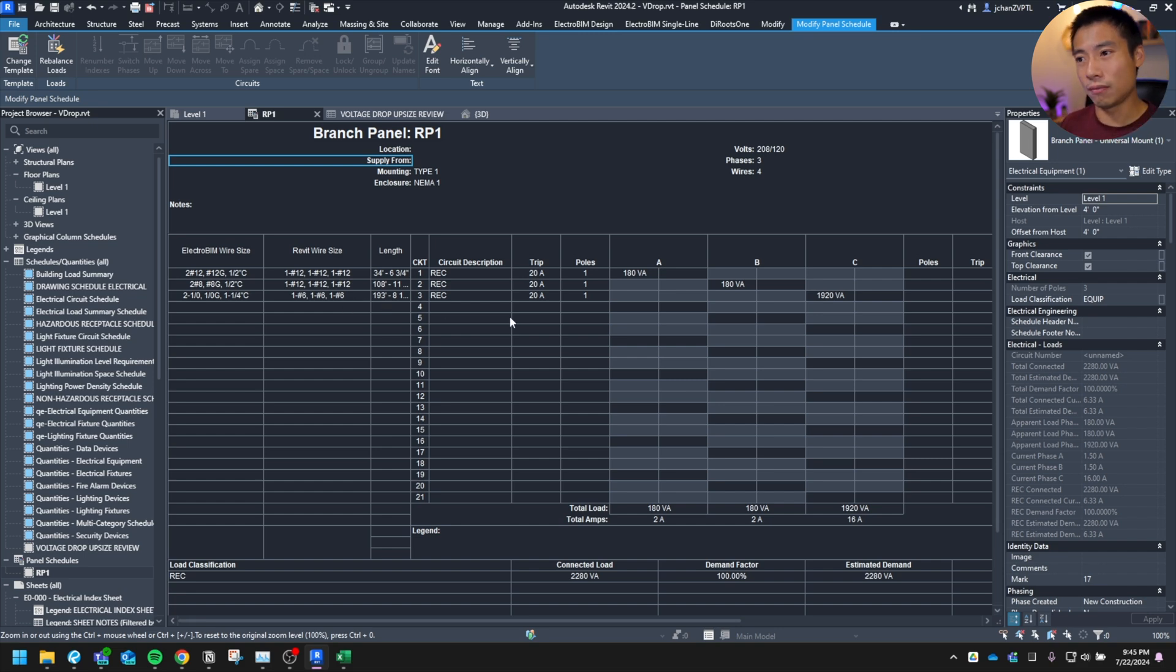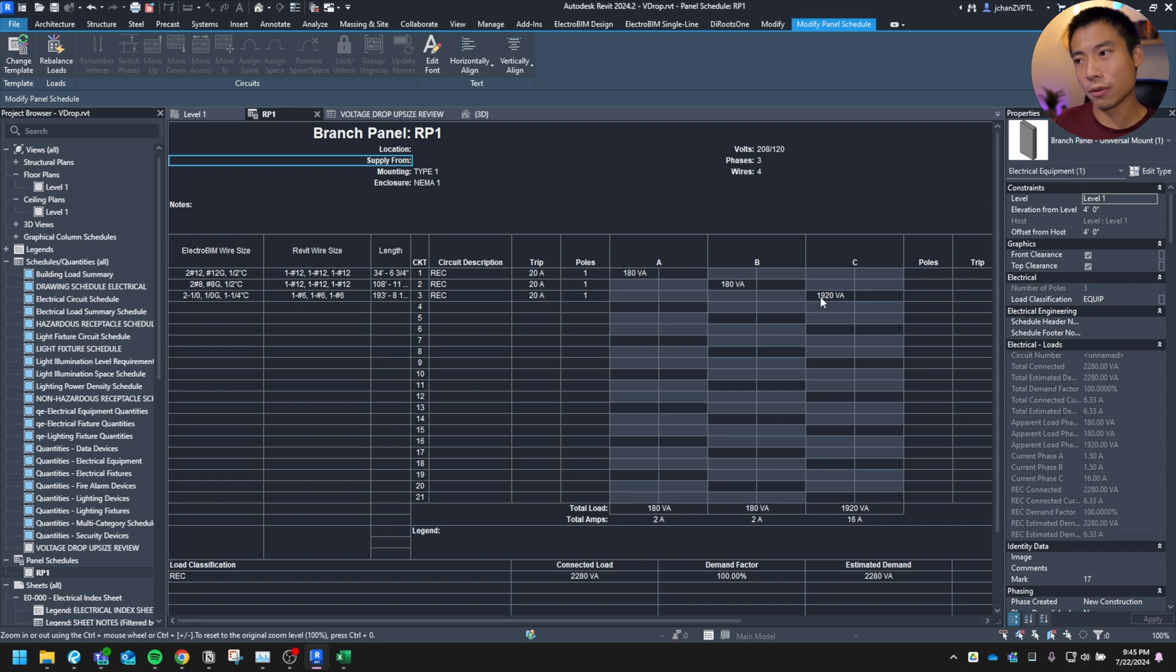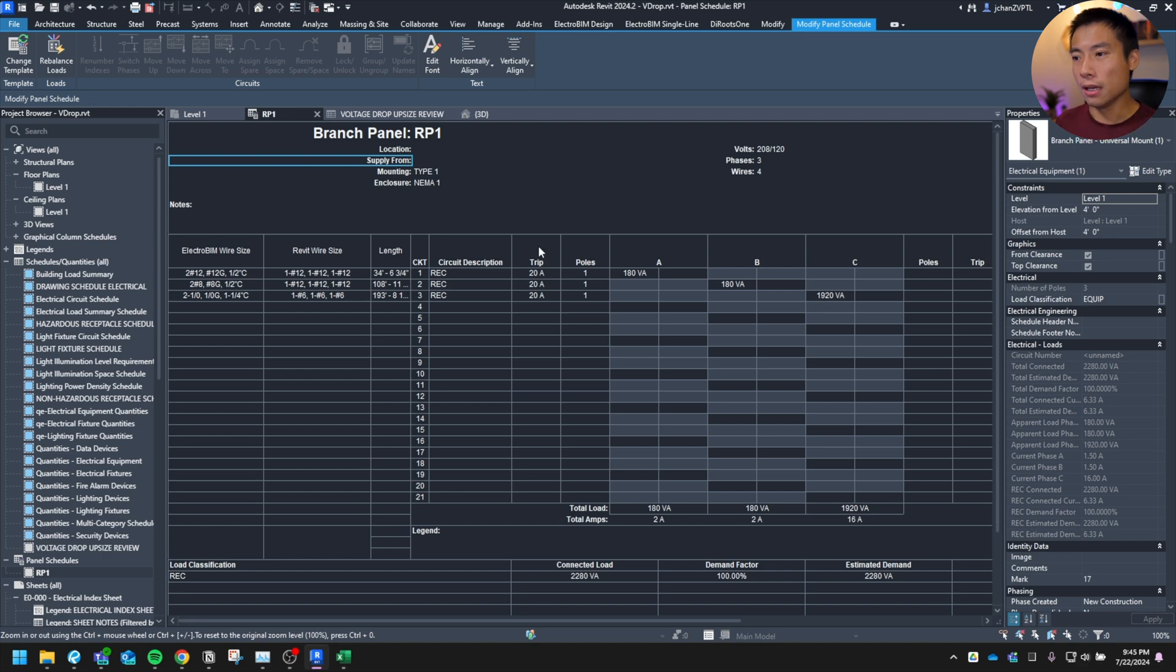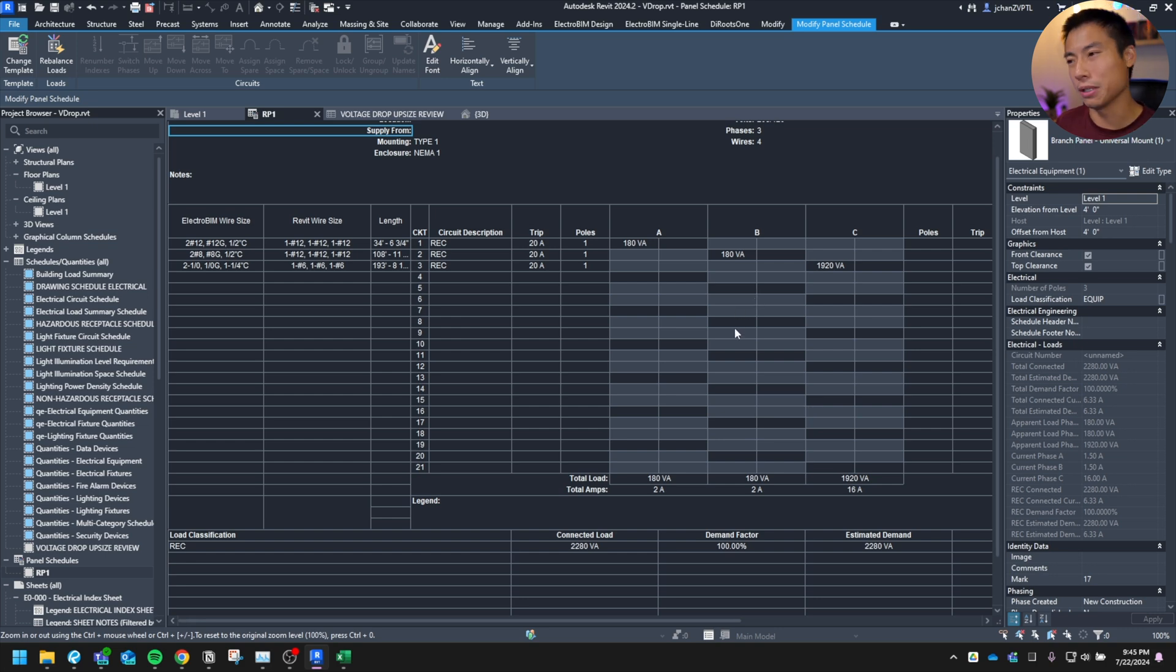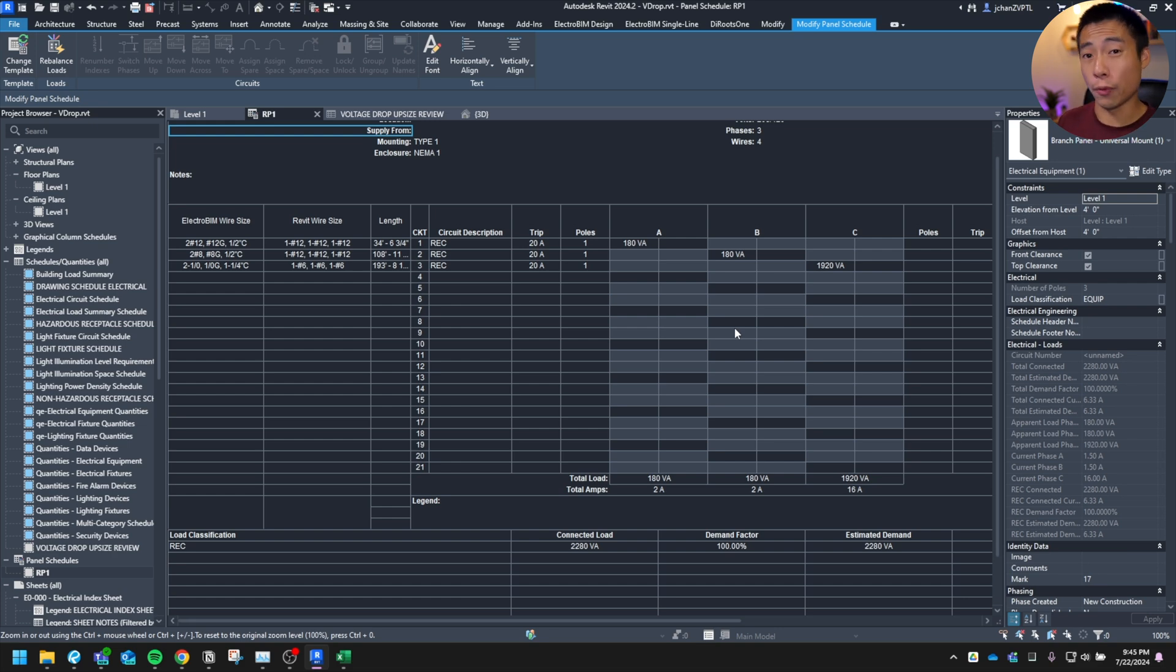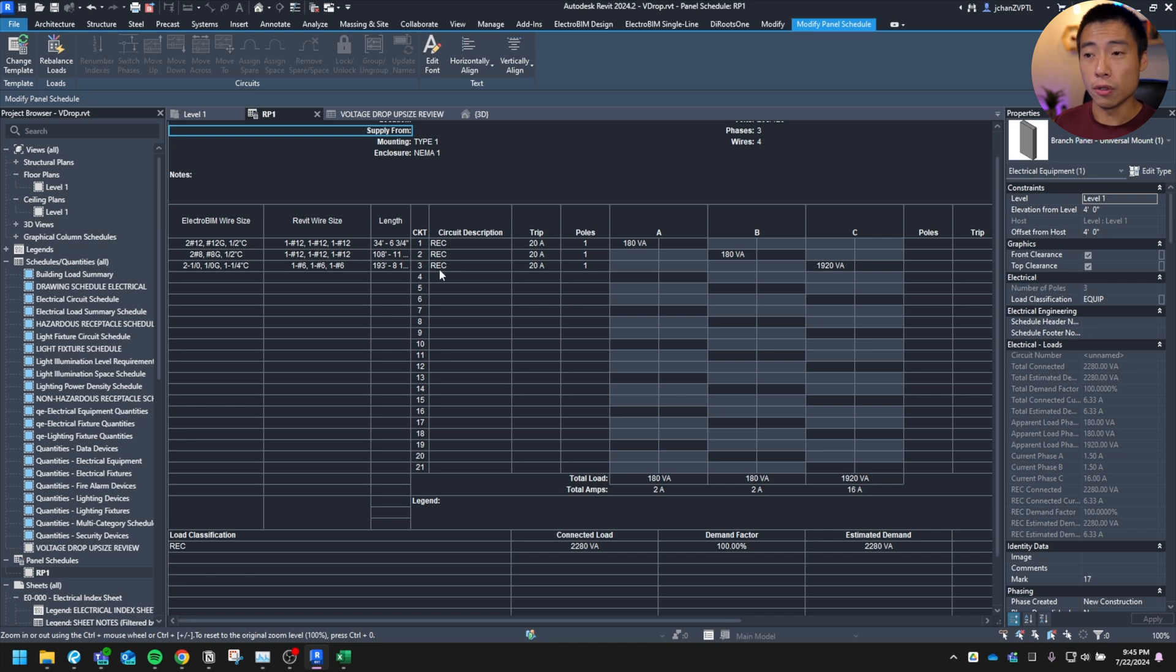But if you had to do it, you would actually need a number six. So this could easily get missed. If you tell someone to put in a general receptacle, they're probably just going to stick 180 VA on there and call it a day. That has other implications depending on how you want to load your panel schedule out, how you want to do your calcs and everything, but that's a different story. I'm not going to harp on that right now. Right now I just want to focus on voltage drop. So voltage drop wise, you could do it this way if you're diligent, or you don't want to show full load on all your dedicated circuits.